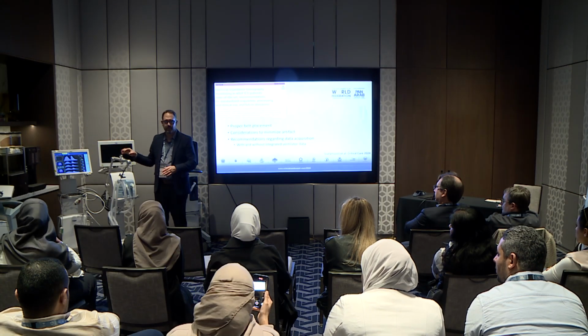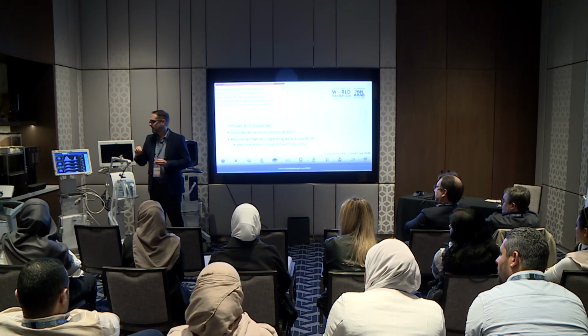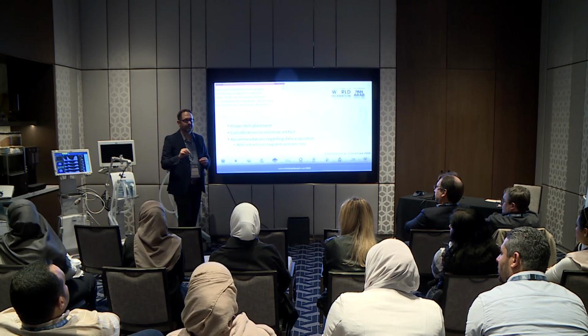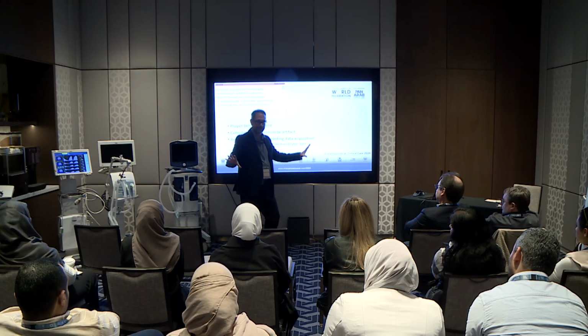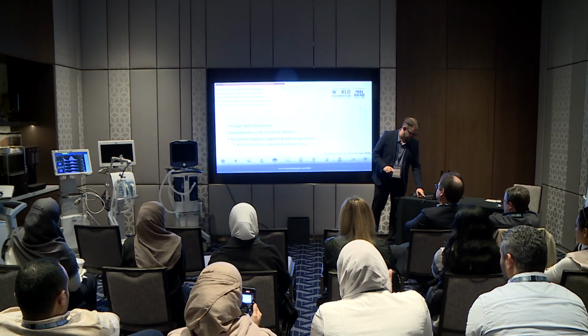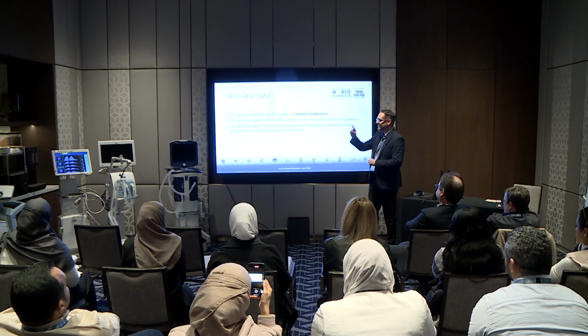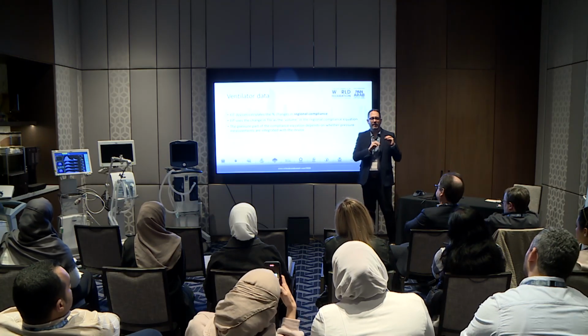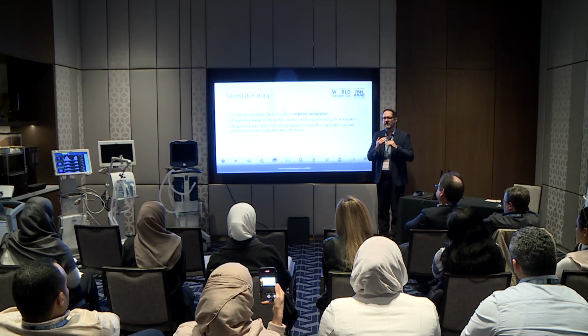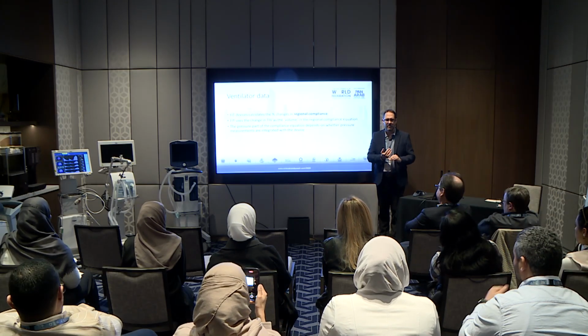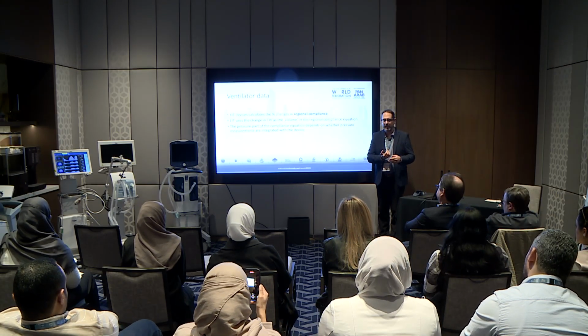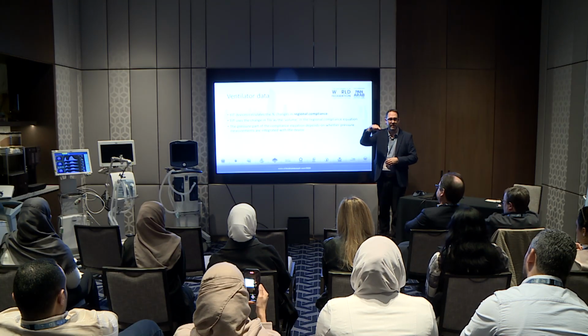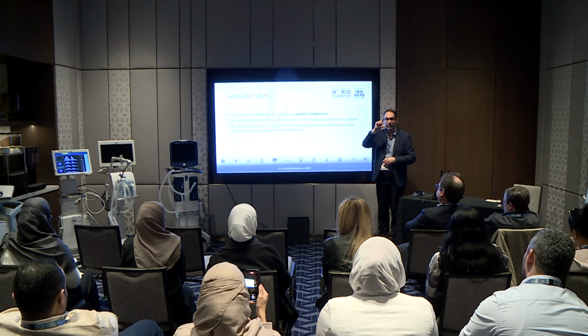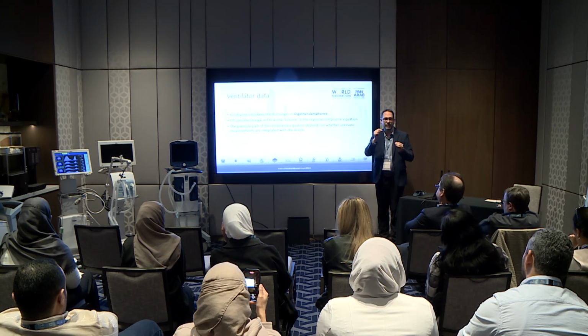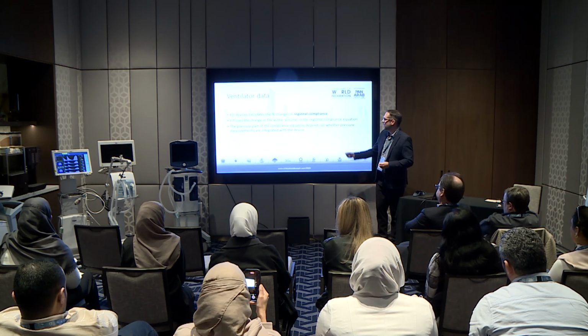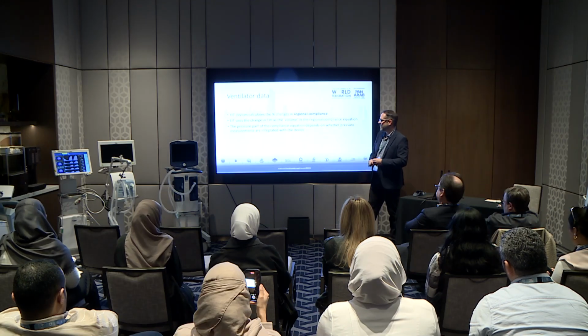But if you connect it to a ventilator, if you want to do certain measurements, you either need the ventilator data or you have to use a certain mode like pressure control and not change the pressure if you want to get accurate measurements. And I think I'll describe that right here. So EIT devices, when you want to do measurements of response to PEEP, it measures changes in compliance. So what is compliance? Mils per centimeter of water. This doesn't have mils, it has those arbitrary units. So it uses those arbitrary units and changes in those units to reflect what changes in compliance would be, okay? So it measures the regional changes of compliance.